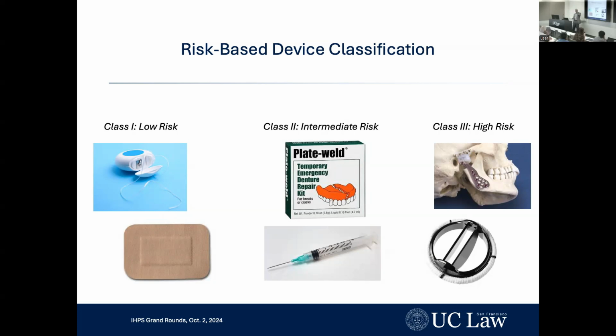Once that device is approved through the PMA process, there's a very good chance the manufacturer is going to modify it. Now you have another new device, and it's a class 3 device, but rather than make the manufacturer go back through the whole onerous process, there are some abbreviated pathways called PMA supplements that allow manufacturers to make these small incremental changes in their devices once they've been approved.